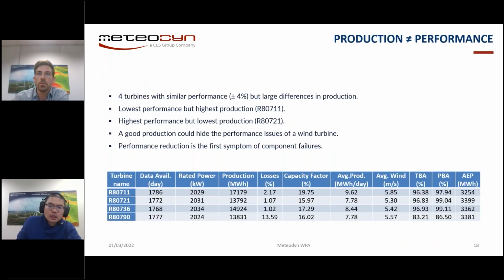Yeah. In fact, for this wind farm, I will show you some interesting points that we found during the analysis of its operation. Firstly, I would like to make clear that the production of the wind turbine is different from the performance. You can see here we have 4 wind turbines in this wind farm, and the performance of those 4 is very close to each other. We calculated a difference of 4%. But here you can see that we have a very different production.